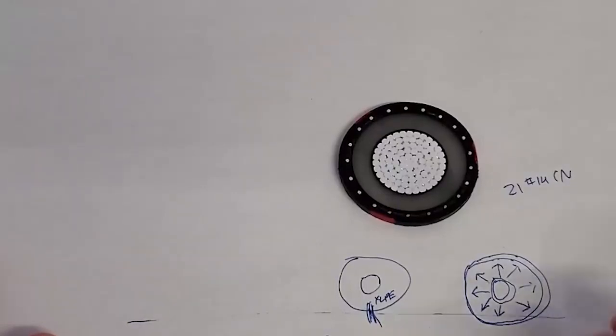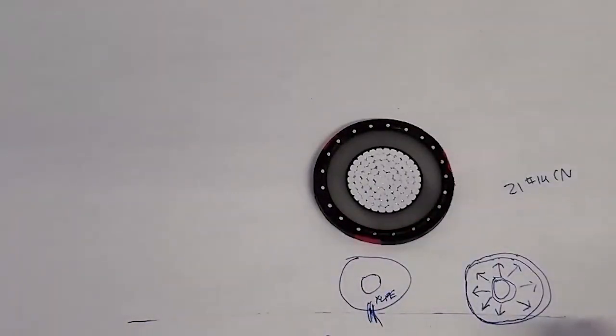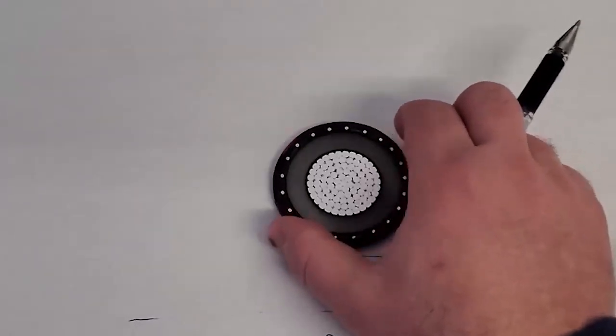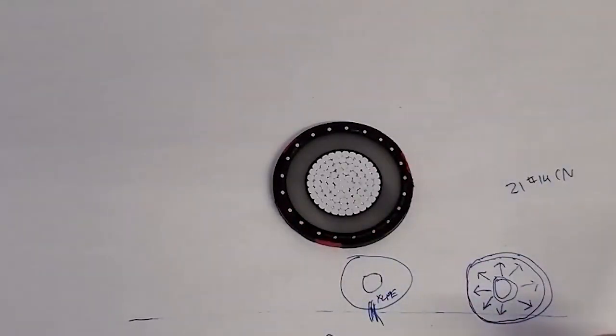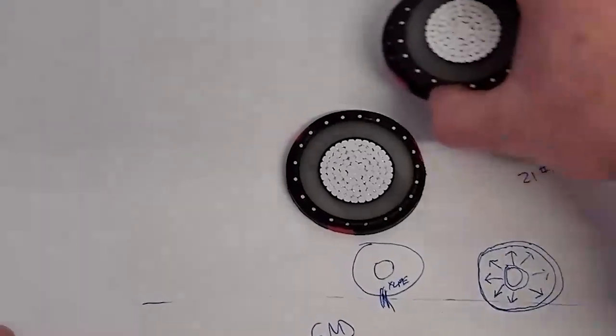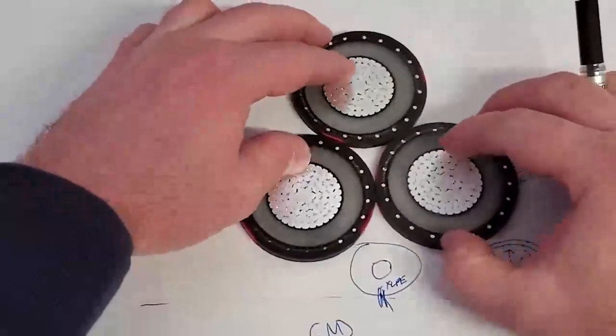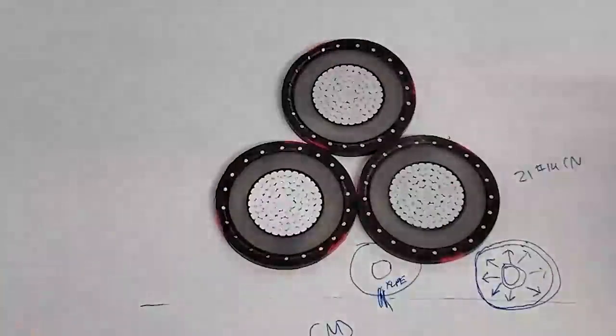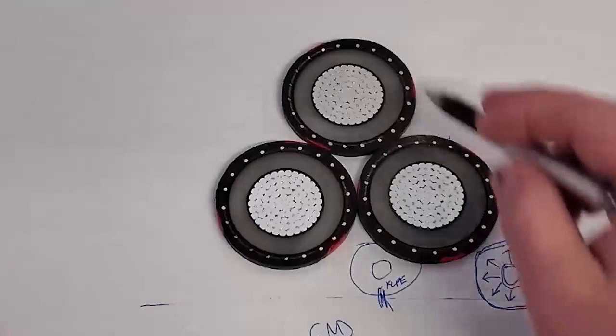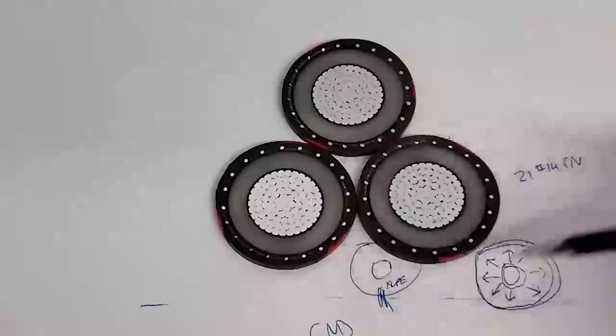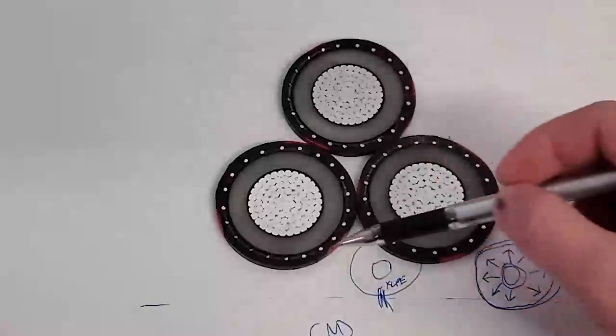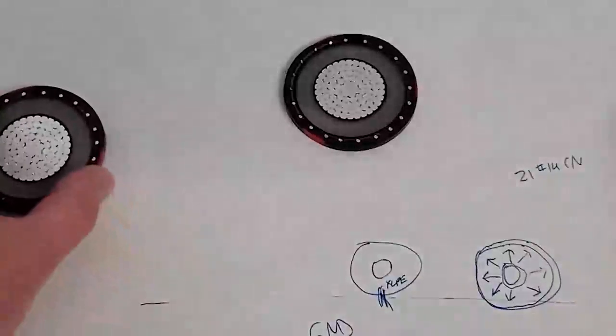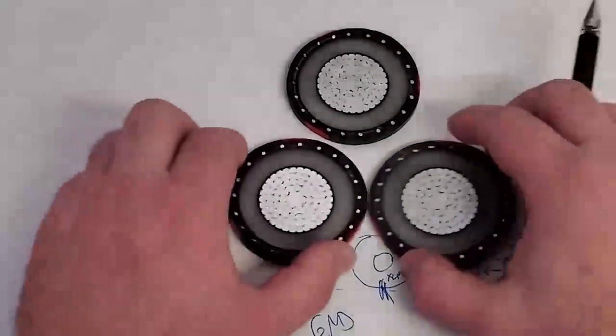So testing for this, you can do high pot testing, which is an older technology. You can do VLF testing, very low frequency testing. I'll put a link up to a video I did on that here right now up in the corner. And then PD testing is the other test as well that we do on this. Another thing that we like to do is we'll trifoil the cable. It's almost all our wind farms we do this way, and what that does is cancel out the electromagnetic field, the EMF, with these cables, and it keeps the heating down. So believe it or not, you'll have less heating like this than you will if these are separated a lot further out. It cancels out that EMF field.